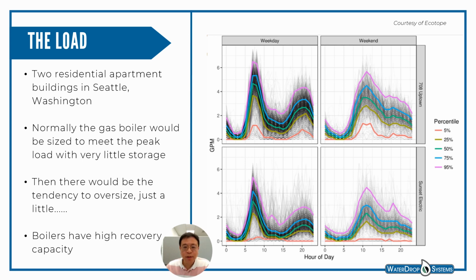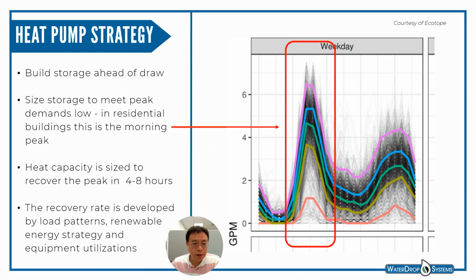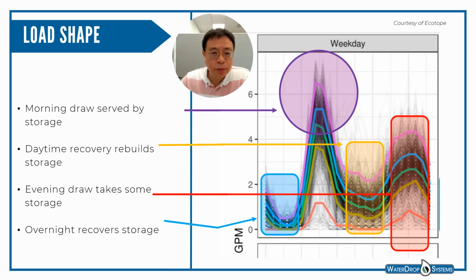The gas boiler is typically sized to meet the peak load with little storage and tends to be oversized. A different approach is applied to the heat pump. We size the storage capacity to meet the peak demand, and the heat pump capacity is sized to recover the energy needed between two peak cycles. There are two peak cycles in a day, one in the morning and the other after work.